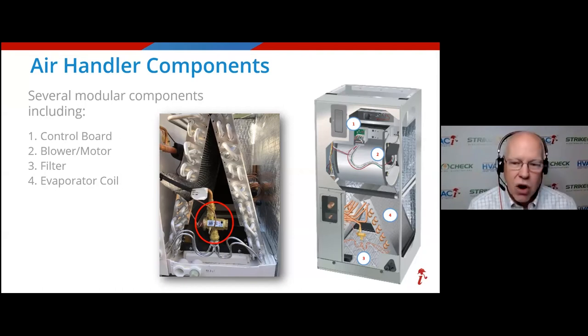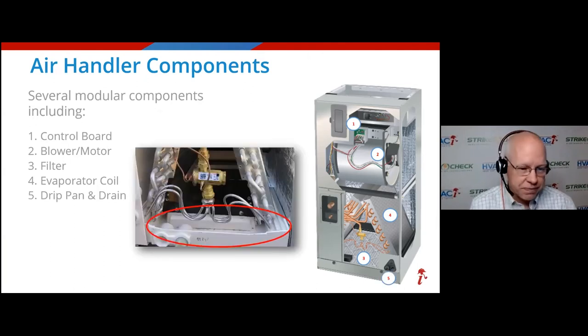So now you know all about that. So you've got to keep the coils clean because if the air doesn't touch the coils, like if they're dirty, you know, it's like having a blanket on it. The air doesn't touch the coils, you don't get good heat transfer. It just kind of ricochets off and you're going to burn up your system. So I can't tell you how many reports we send out where things end up being not covered because people simply didn't maintain their system. They didn't clean the coil outside and they didn't change their filters. They didn't get good heat transfer and they burned up their compressor. So anecdotally, at home, make sure you're doing those things. All right, so let's move on.